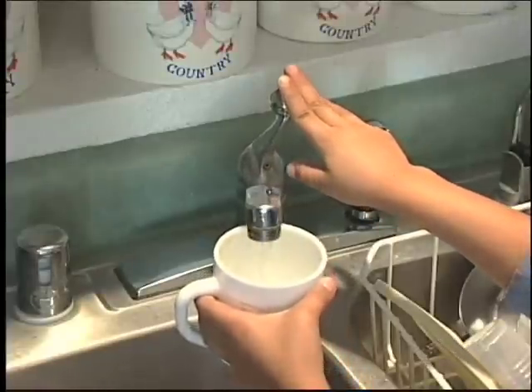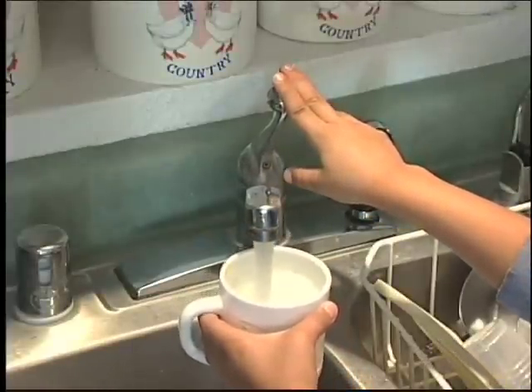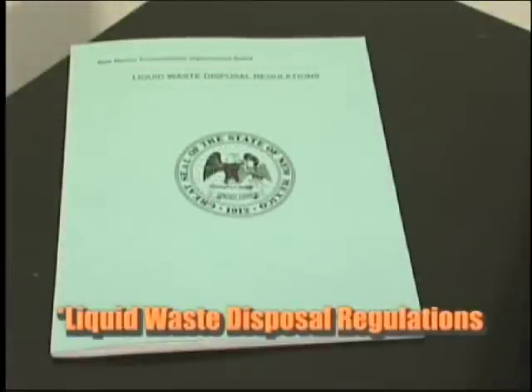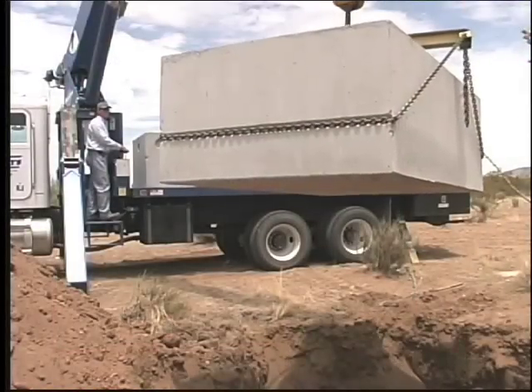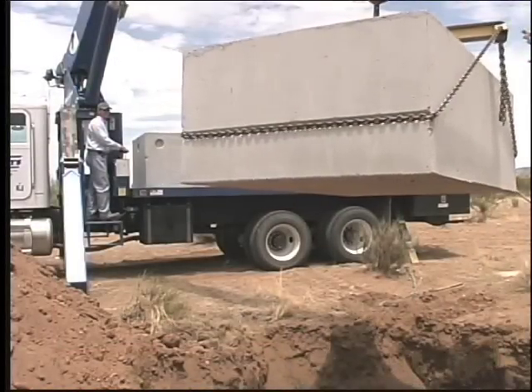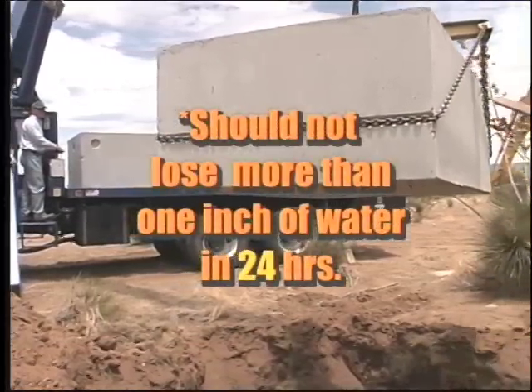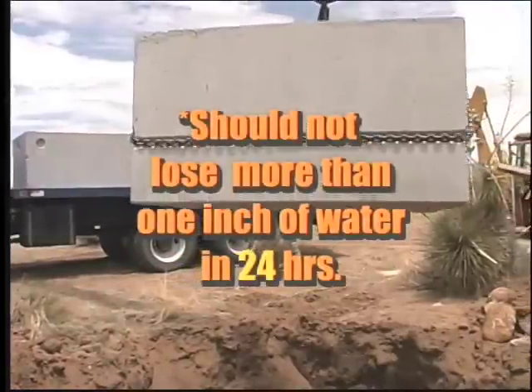For the protection of your drinking water, it is important that the tank be watertight. Many regulations require the homeowner to fill the tank with water and measure the loss of water over time. This is an excellent idea even if it is not required. A watertight tank should not lose more than an inch of water in 24 hours.